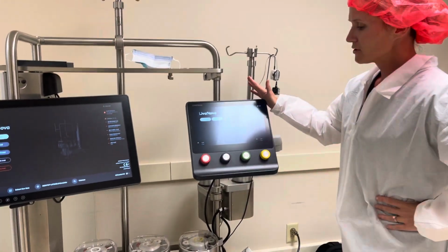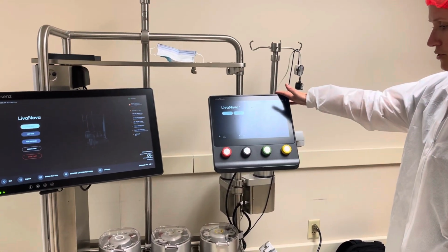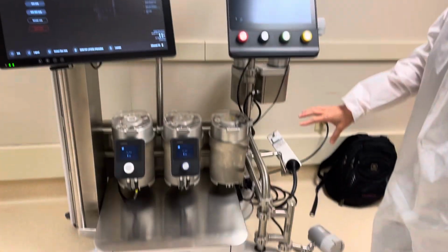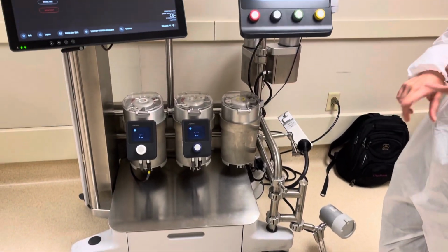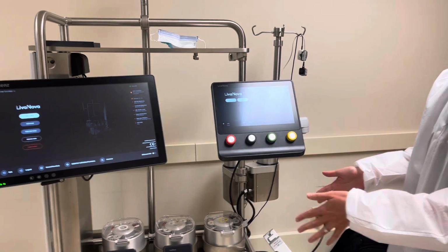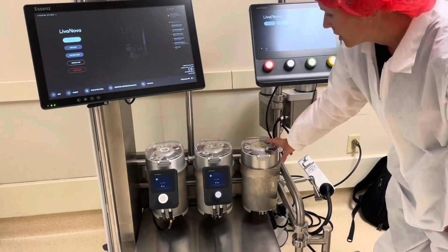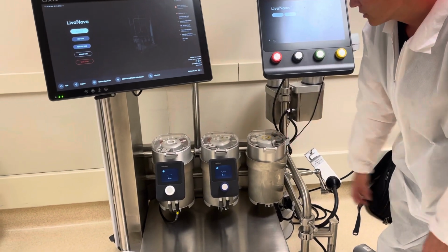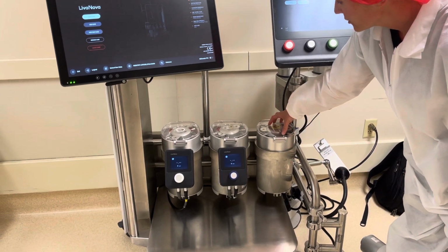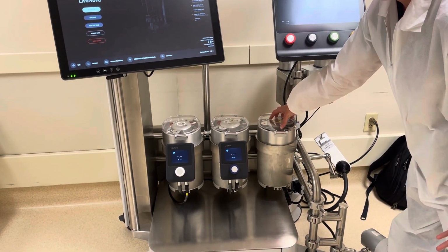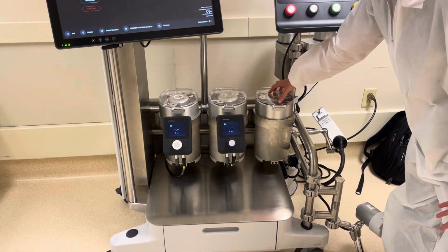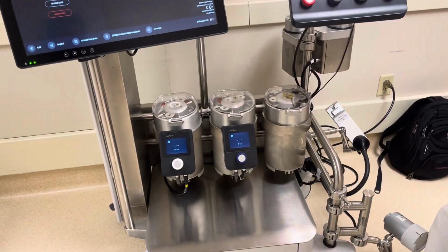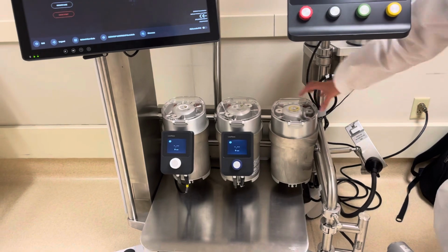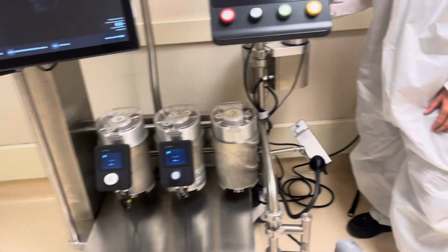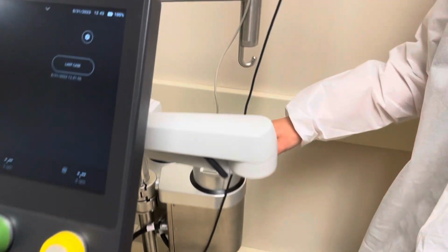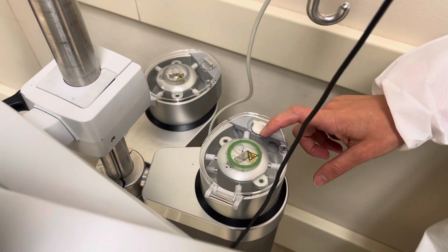All right. So the big difference now is you're going to see that the base is one size fits all. Unlike with the S5, where you had a 3, 4, 5 position base, now it's going to be one size, because all of our pumps are going to be mast mounted. You'll see that we did not change the inner workings of the pump. They are the bread and butter of our machines. They're fantastic. They work well. So we kept those. The sizes are going to be the same, but you'll see now with these small rollers that you can actually purchase them separately.